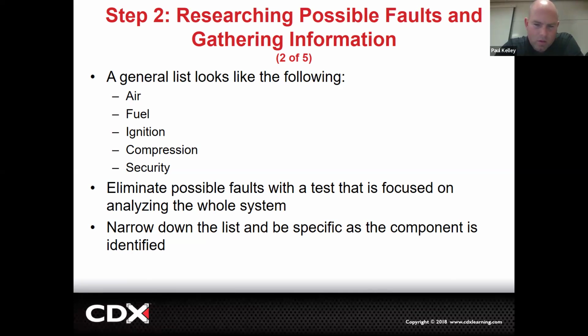If, let's say, the blower motor is not working, I can eliminate all that refrigerant pressure stuff and just narrow down to the blower motor, because the blower motor is not coming on. The customer may not say my blower motor doesn't work, the customer may say my AC blows warm. But you've got to get in and start eliminating some things. If the blower motor is not running, we're more worried about the blower motor, we don't really want to look at refrigerant pressures and whatnot. Kind of makes sense? So narrowing it down is a process of elimination.